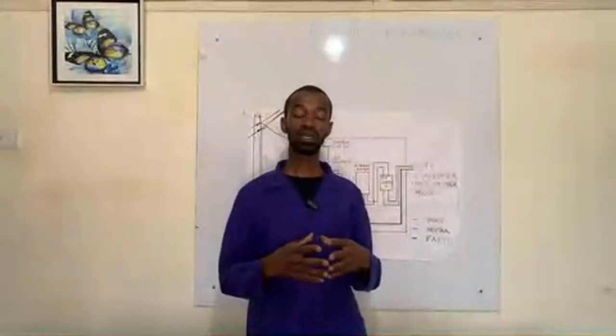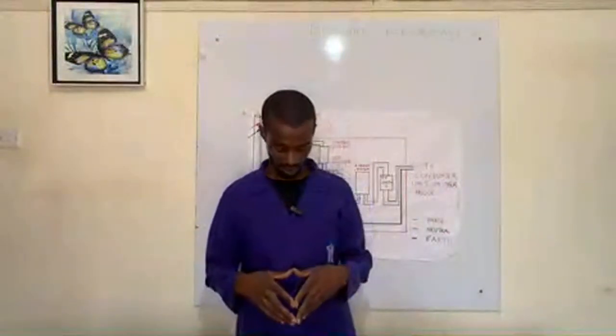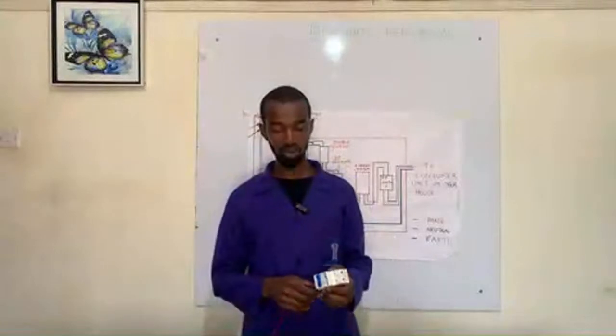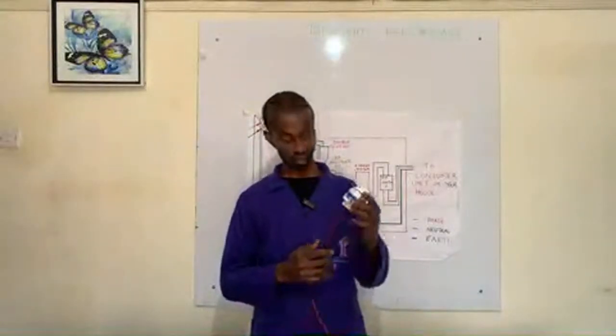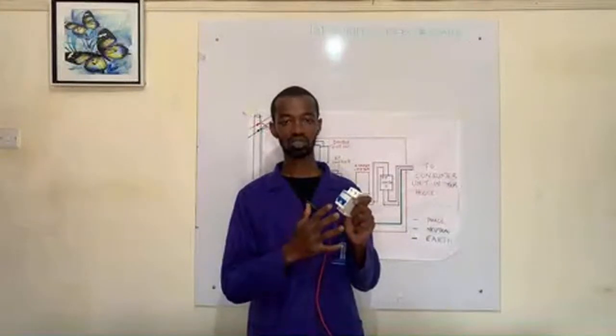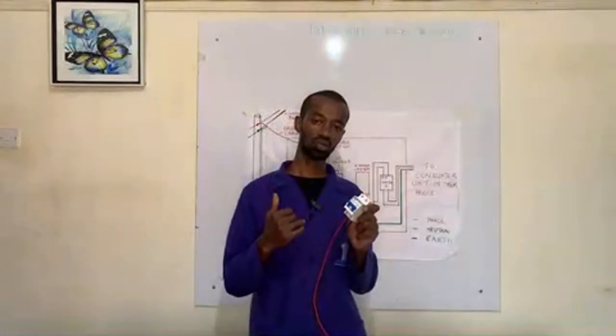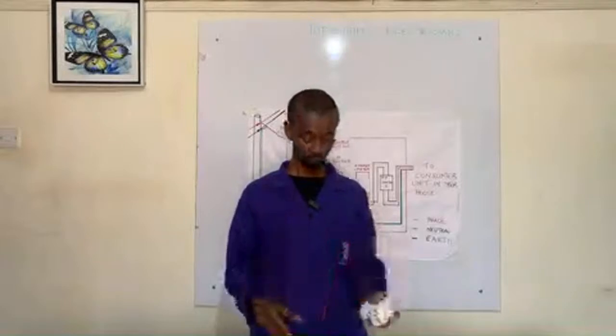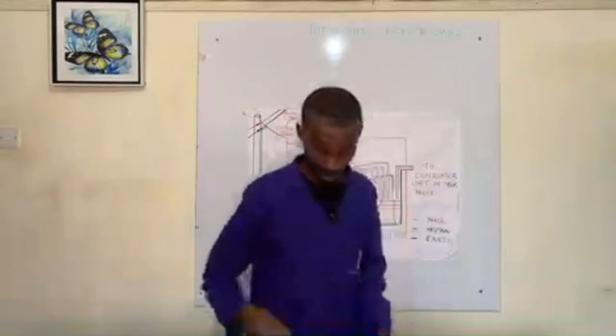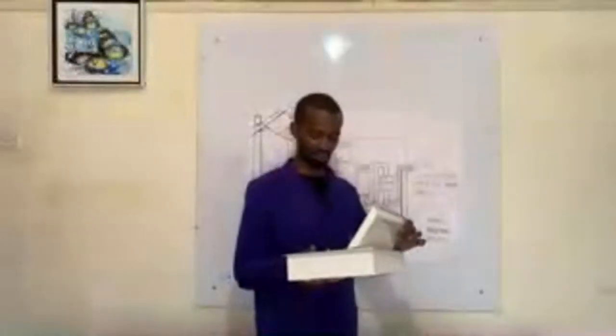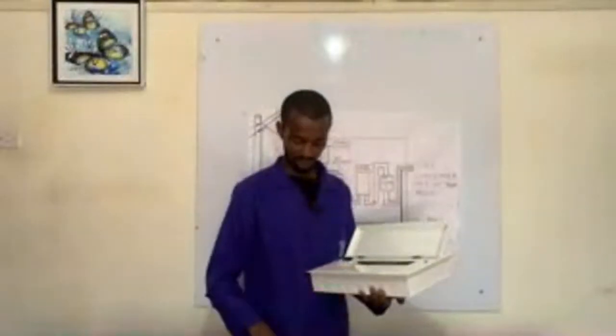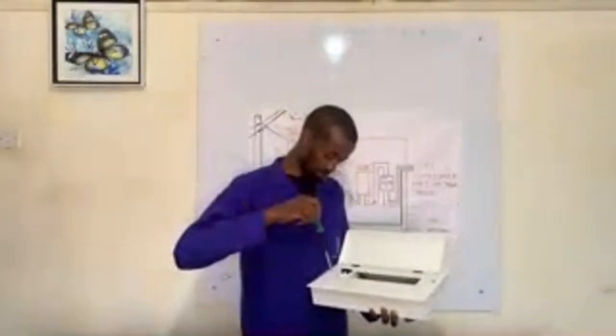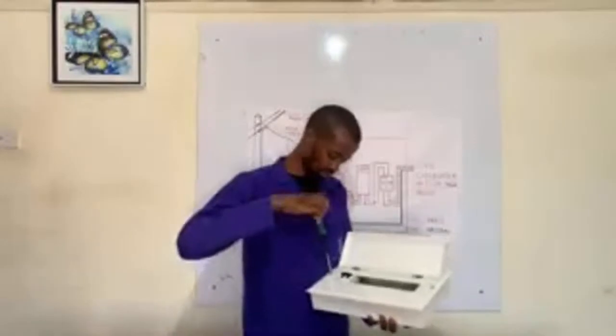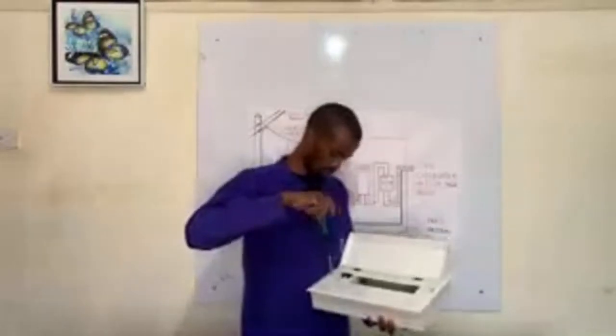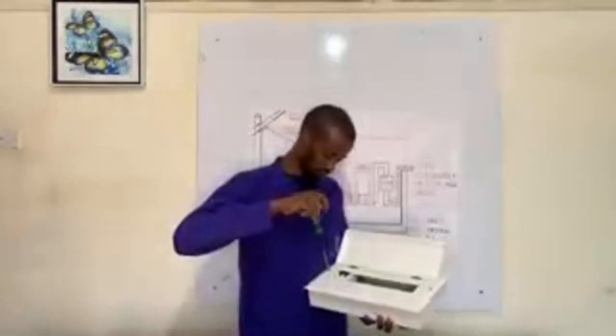If you have a bulb that is flickering, you need to check on that. Most people who ask me about loose connections, I refer them to check those connections in the meter box as well as in the consumer unit. Specifically, when you get to the consumer unit, there is something you can also check. On the consumer unit, there is what we refer to as a neutral bar, and we also have a bar for the earth connection.